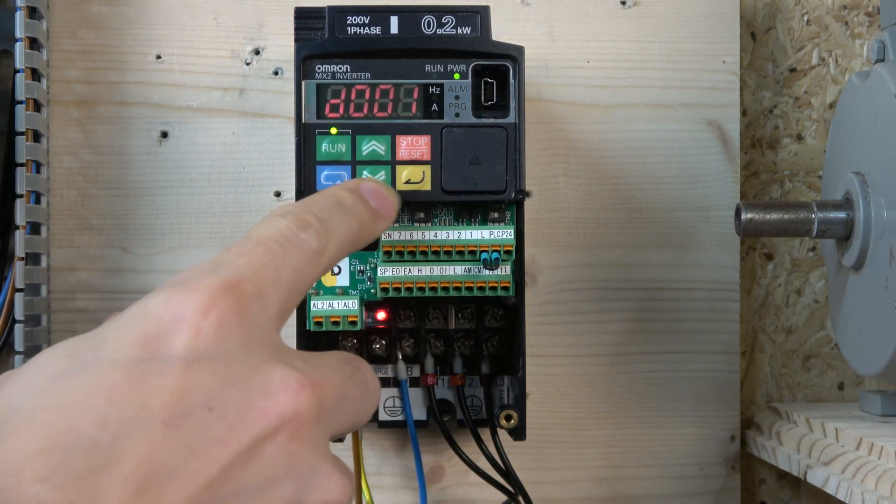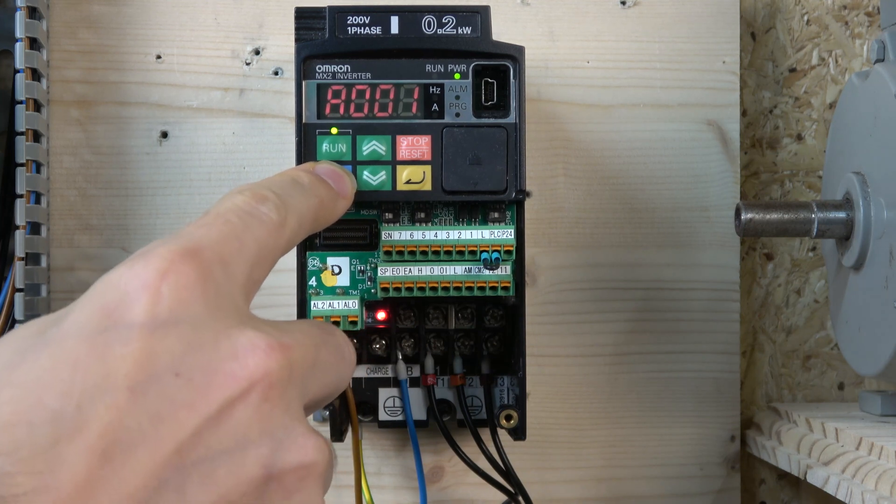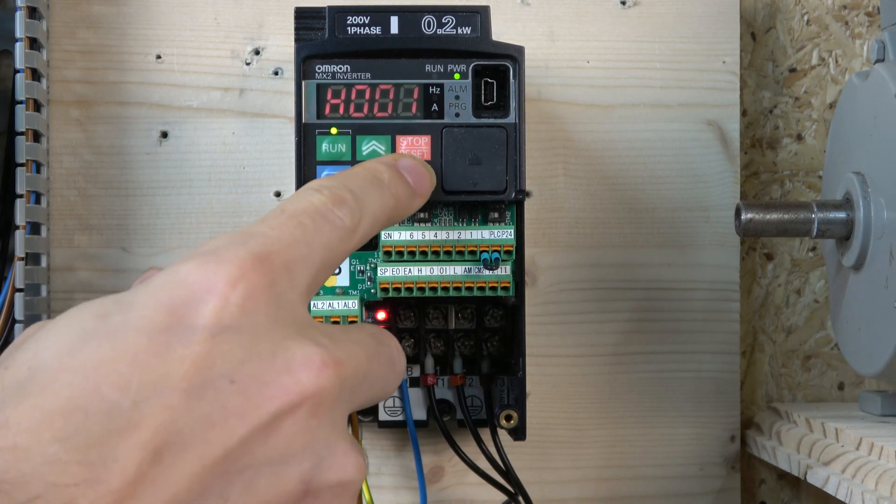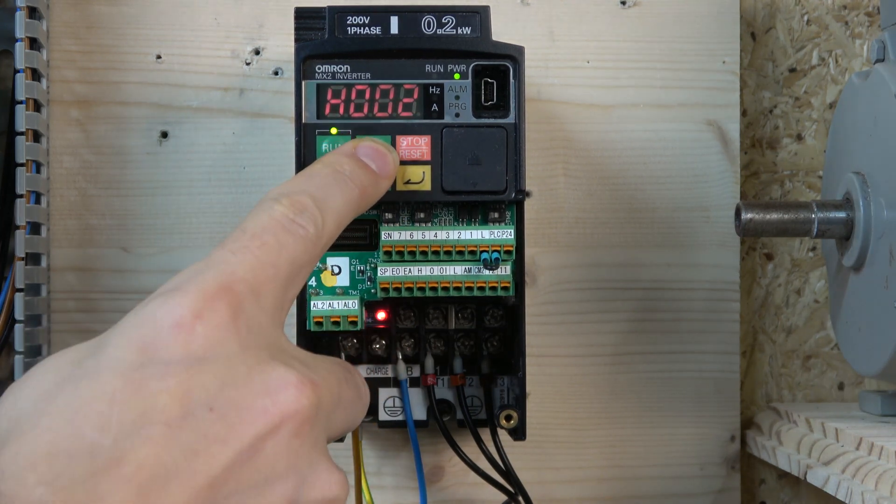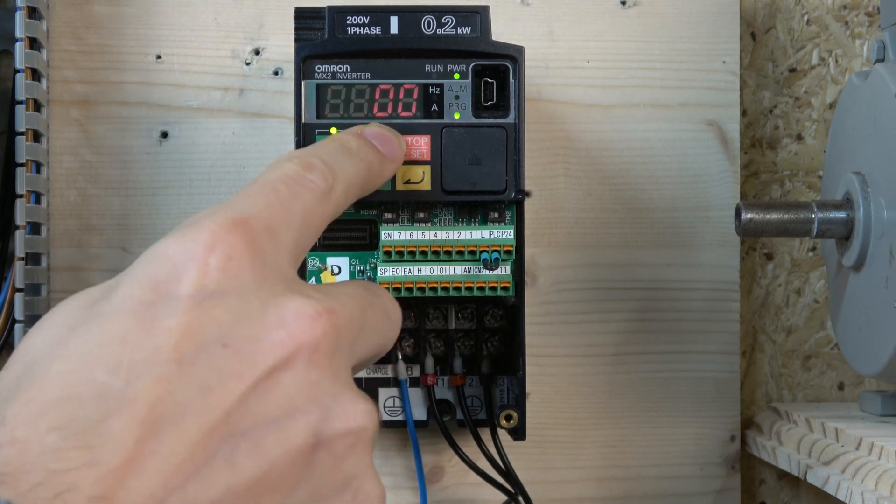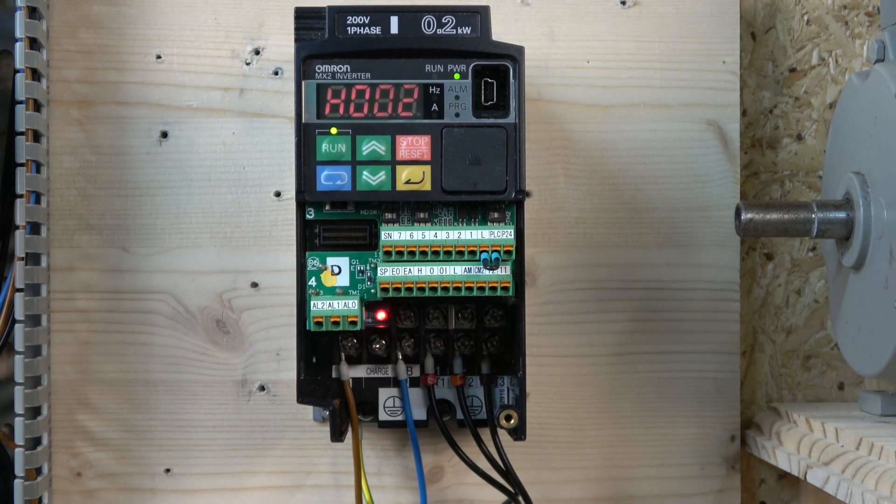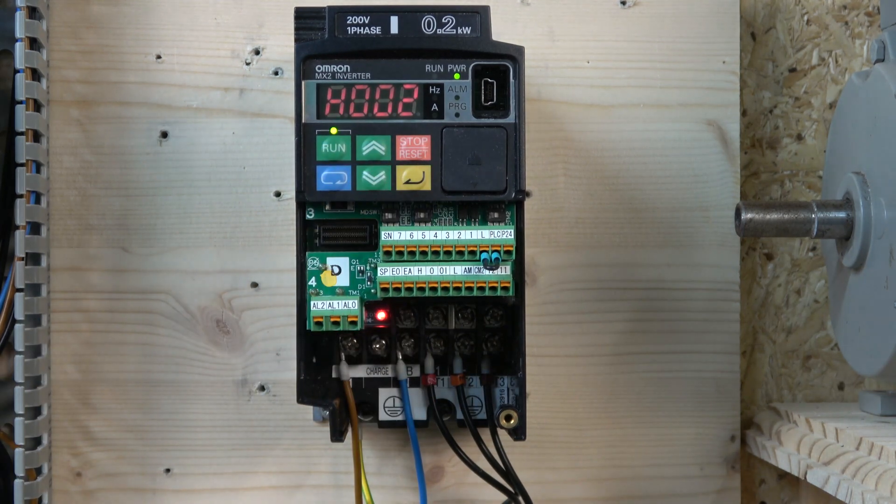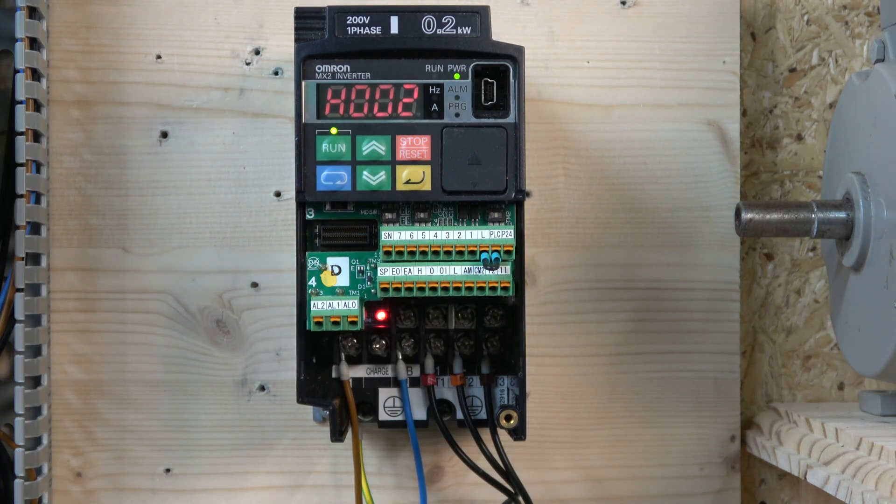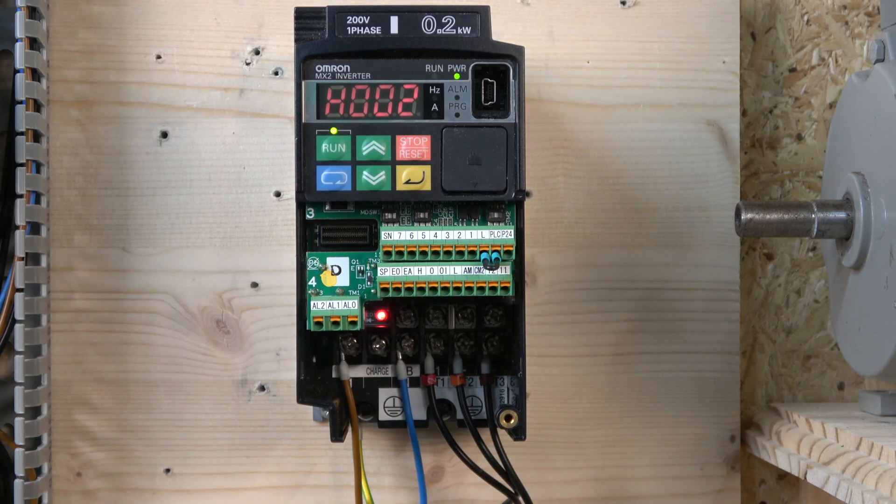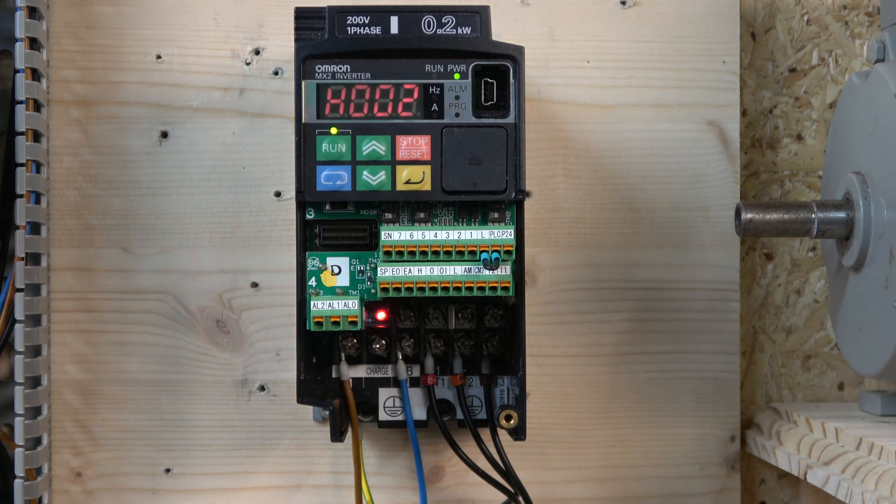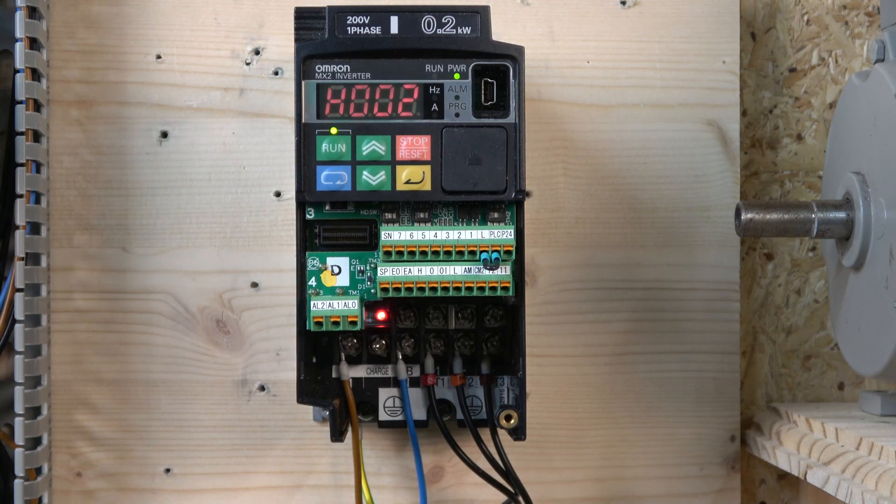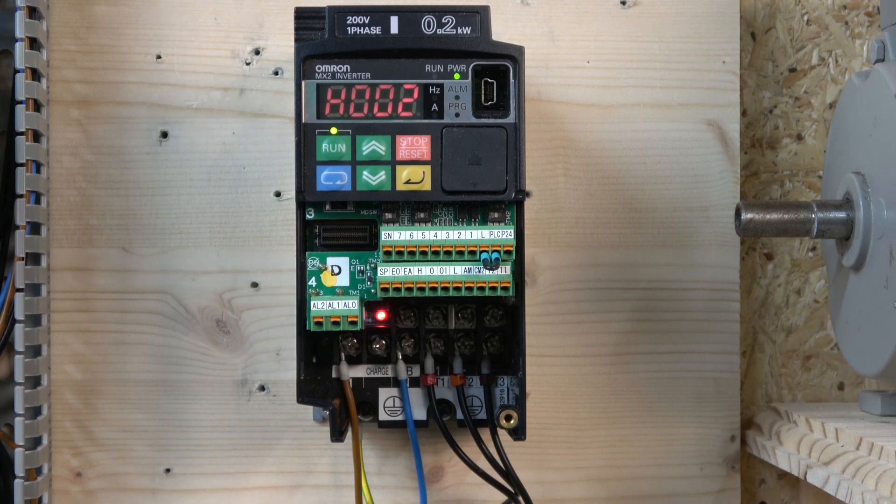Once that's done, click that. From there on, you need to do one more thing. Go to the H parameter again, go to parameter H02, and change that to 2. Once you've done that, you're pretty much done. It has taken all the parameters it measured and done its business. Auto-tune and motor data are all complete. Our data is edited and it's ready to go.